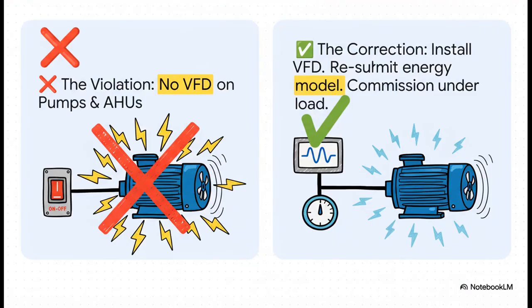You know, the days of simple on or off systems are pretty much over. If you have big pumps or air handling units just running at 100% speed all the time, you're toast. It's a violation of energy codes like ASHRAE 90.1. The fix? You need to install a variable frequency drive, a VFD, which lets the motor intelligently ramp its speed up and down to match the actual demand.